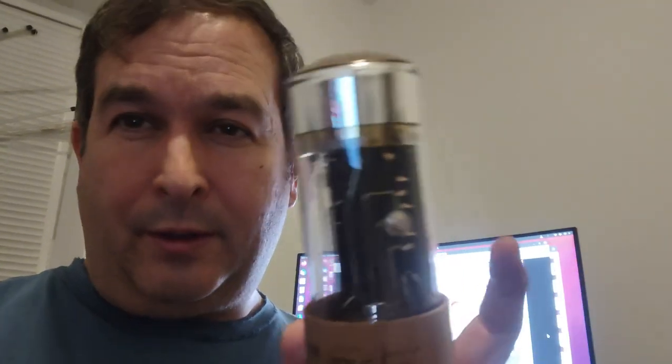It knocks an electron off and it's amplified through a series of what they call dynodes. It rattles back and forth using secondary emission where one electron can knock off more than one electron, maybe two or three electrons. They'll be accelerated to the next dynode and each electron there will amplify that many times as well. By the time you get down to the bottom, this is a ten-stage photomultiplier, the current can be amplified millions of times so you can detect single photons.